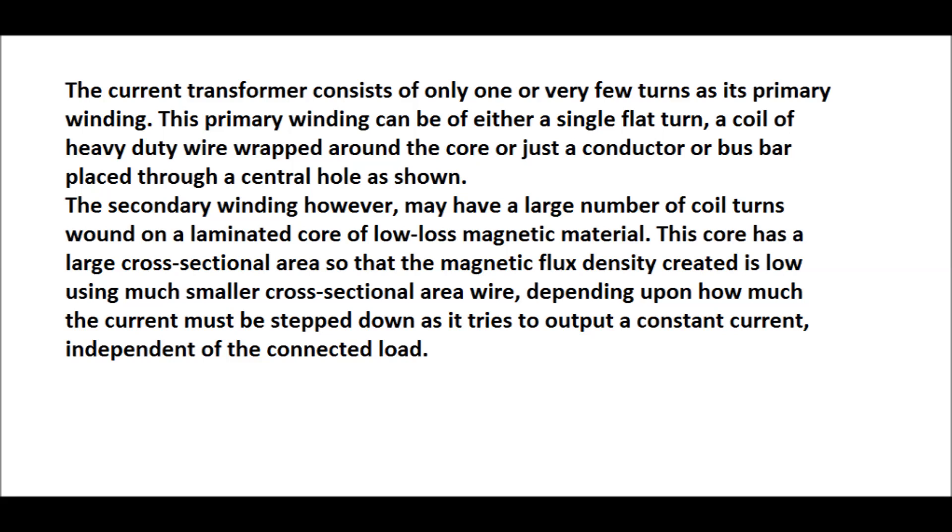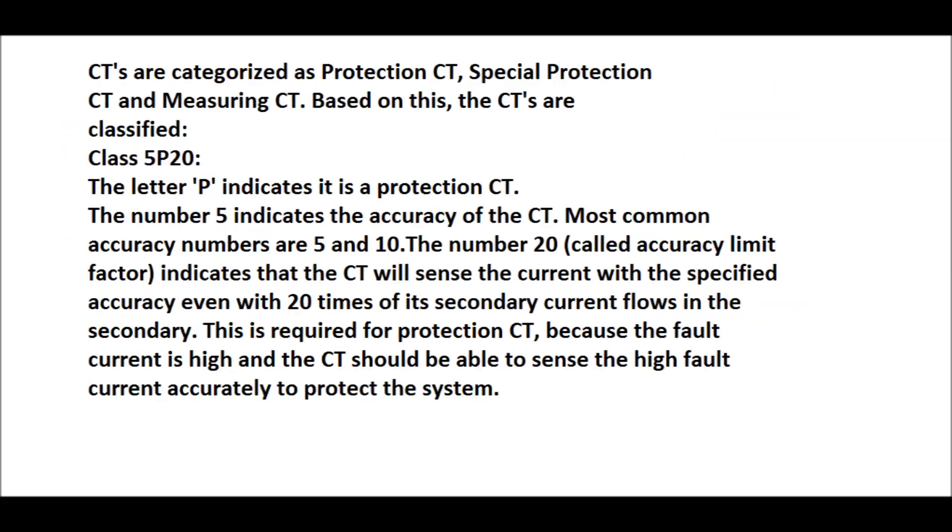The secondary winding, however, may have a large number of coil turns wound on a laminated core of low-loss magnetic material. This core has a large cross-sectional area so that the magnetic flux density created is low using much smaller cross-sectional area wire, depending upon how much the current must be stepped down as it tries to output a constant current independent of connected load. However, the CT secondary always remains shorted through its ammeter or relays.